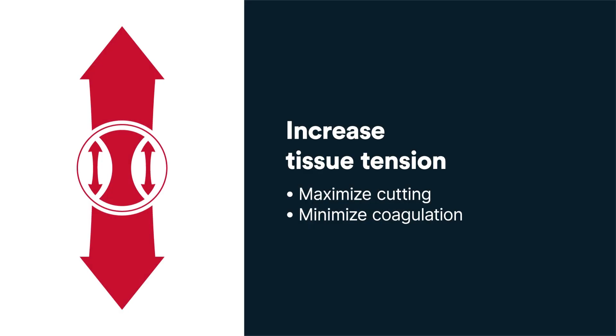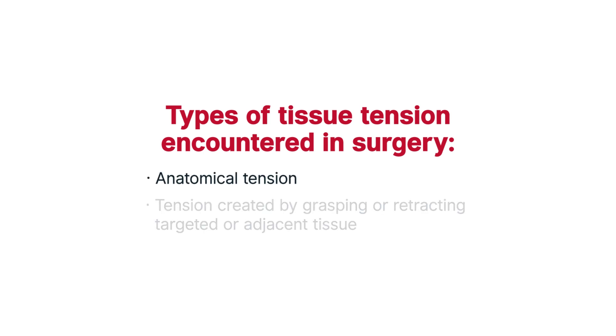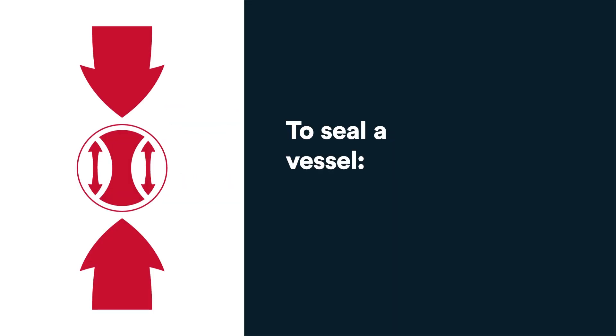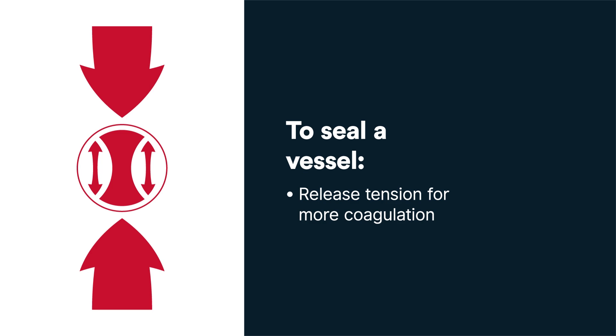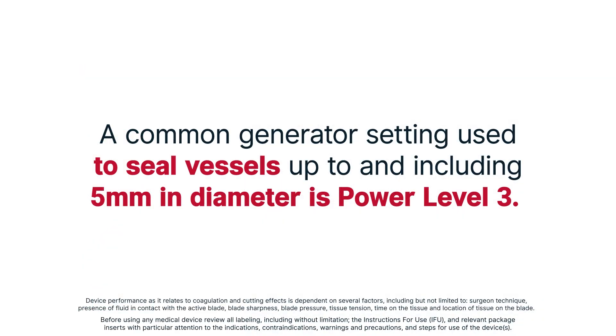Tissue tension. Like blade pressure, adding tension to the tissue maximizes cutting and minimizes coagulation. There are generally two types of tension encountered in surgery: anatomical tension, and tension created by grasping or retracting targeted or adjacent tissue. To seal a vessel, it is recommended to release tension on the tissue to allow for more coagulation, as well as use a lower power setting. A common generator setting used to seal vessels up to and including 5 millimeters in diameter is power level 3.